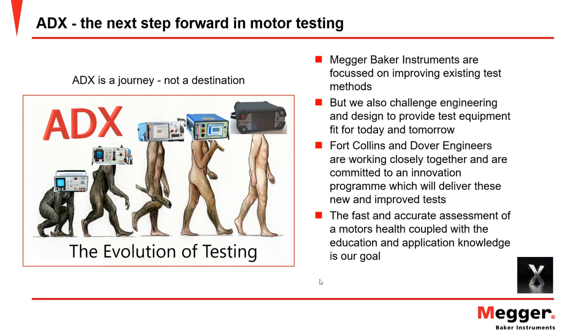Now, if you can imagine, we're also trying to start an electric motor. So that spark, which is several hundred and maybe 1,000 volts higher than the supply voltage because of the arcing condition, is also compounded by the effect of high current during the startup. So if we have a full load motor that's 100 amp full load, on startup, during those few instants while we've got that high voltage spike and are trying to start the inertia of the motor from standstill, we're looking at 8 times that full load current. So we've got 800 amps, and maybe on a 415 volt motor during that arcing period of the startup, it's probably going to be 2,000 or 3,000 volts.